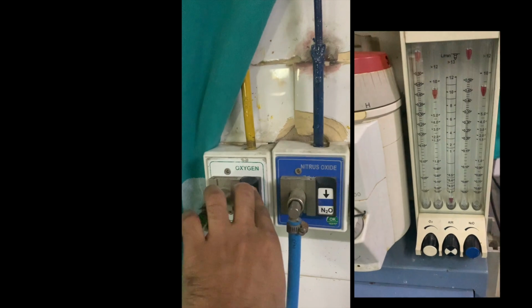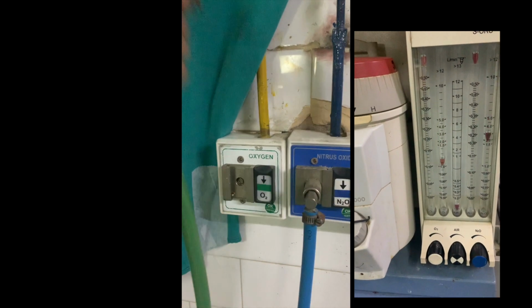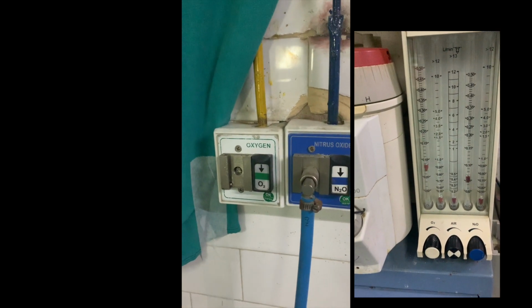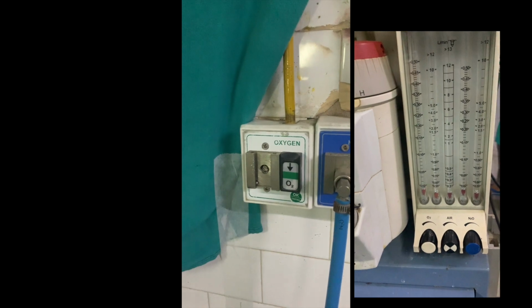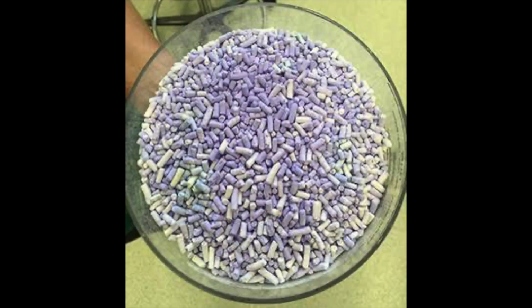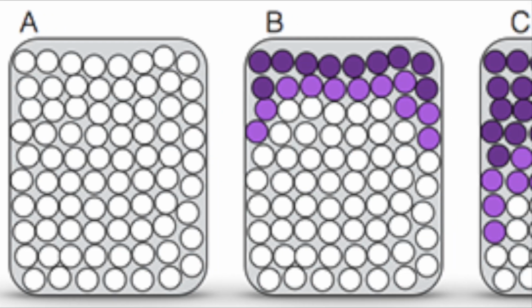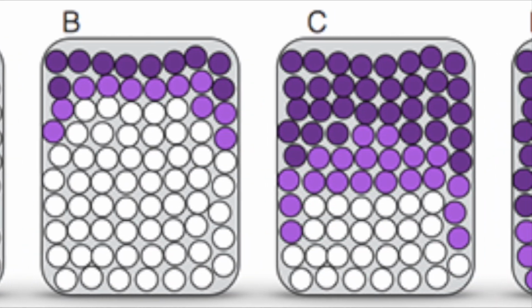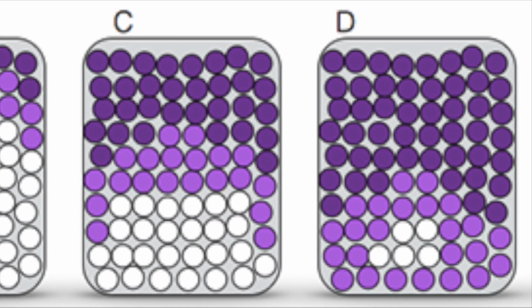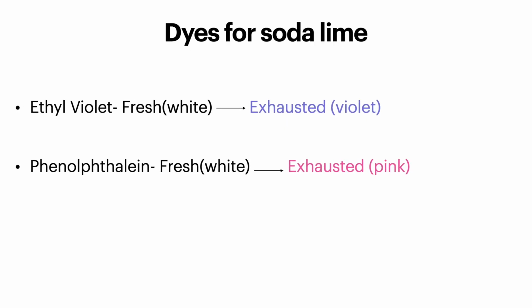Check the oxygen pressure failure device. Create a hypoxic mixture by disconnecting the oxygen pipeline and look for the change in flow of gases. For the carbon dioxide absorbent, that is soda lime, look for the color change. If more than 2/3 of the canister is filled with exhausted soda lime, then get it changed.